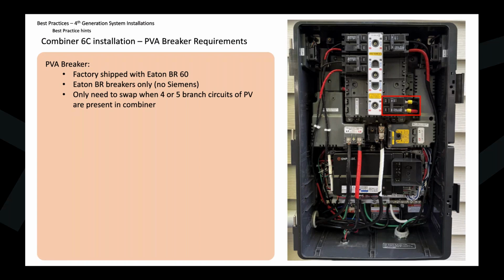If you do 3 branches of PV or less, no need to change it. If you do 4 branches, or that 5th branch circuit, you'll need to pop that out and put an Eaton BR80 or BR100 in there. Again, Eaton BR, no Siemens, and you only need to swap that when you go to that 4th and 5th branch circuit.